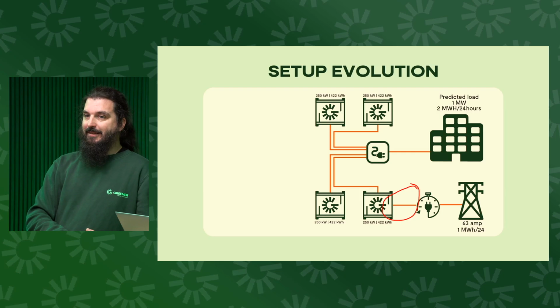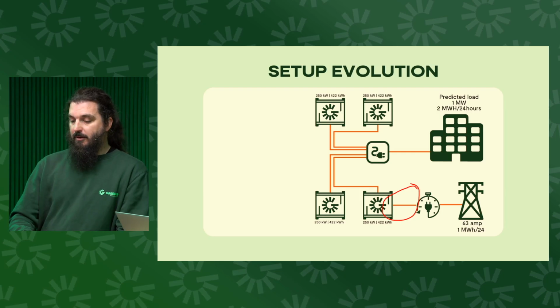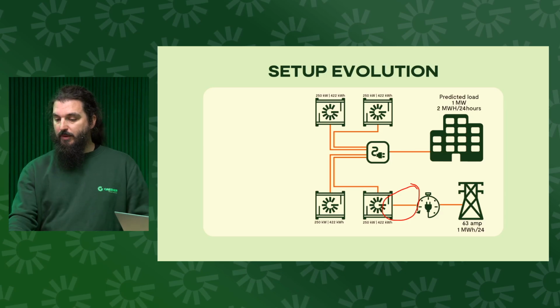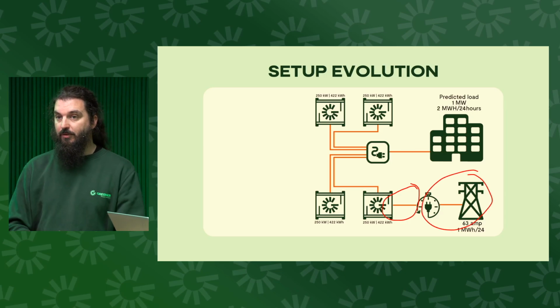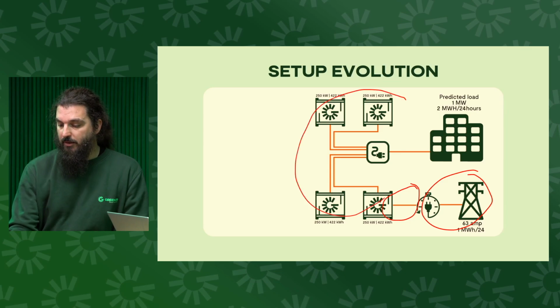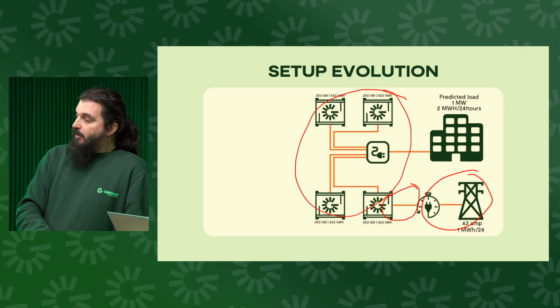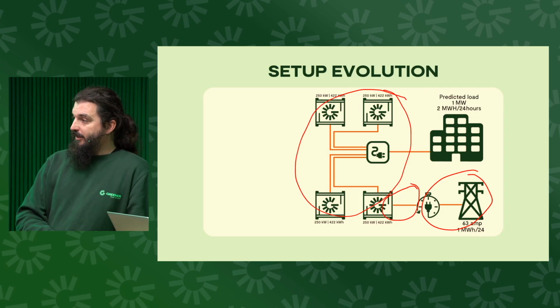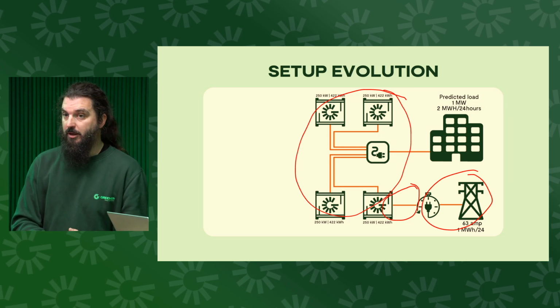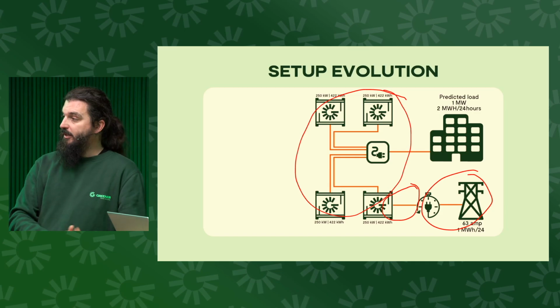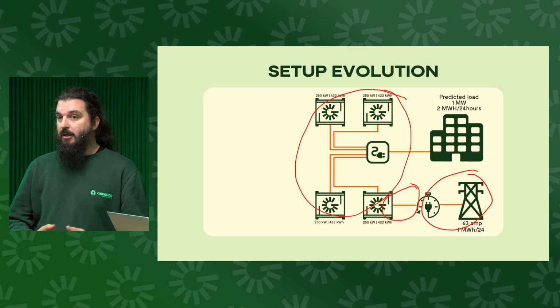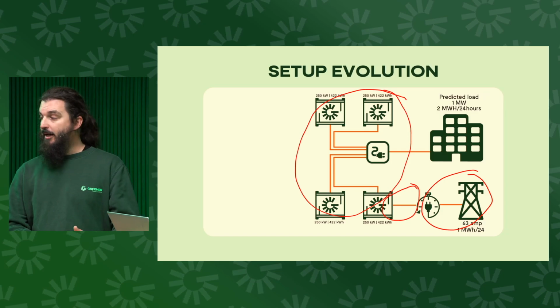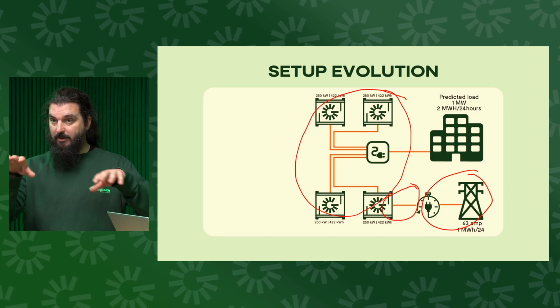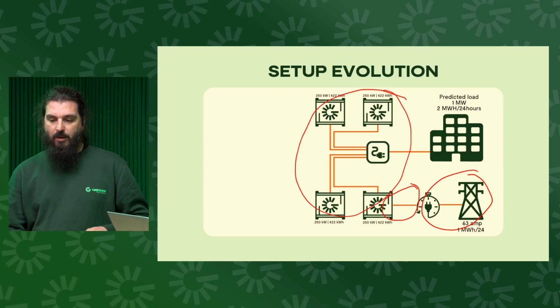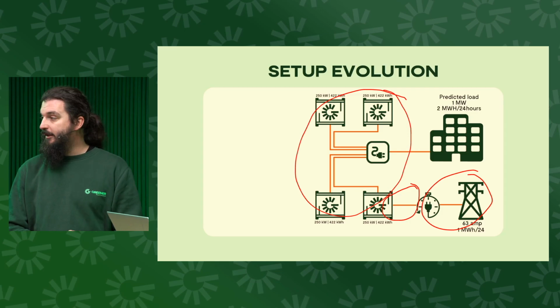We use our AC/DC/AC technology to make the frequency separation between the DSO, so whatever's happening in the grid, and our own microgrid, which is on this box. So we go through 0 hertz through DC, and then make it do whatever the frequency on the secondary side is in our microgrid. And because we control the frequency there, we can use that frequency for the batteries to communicate to each other how full they are individually, and then balance their state of charge, and equally participate in the energy that needs to be delivered.